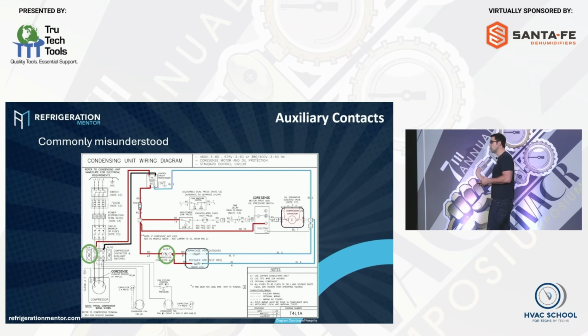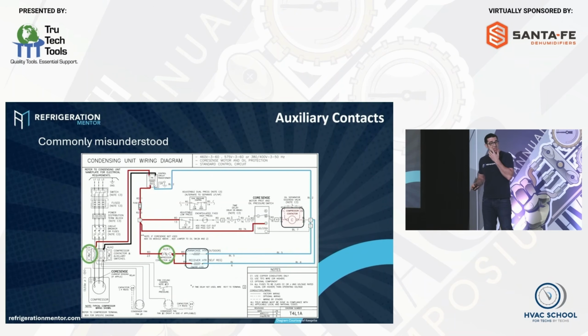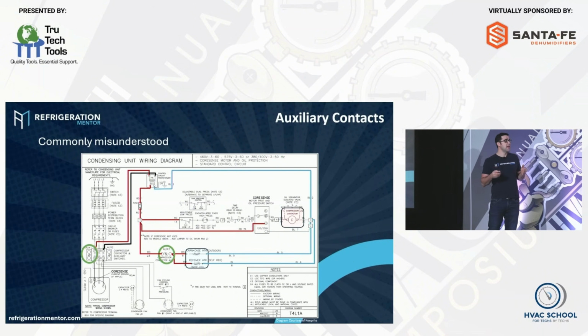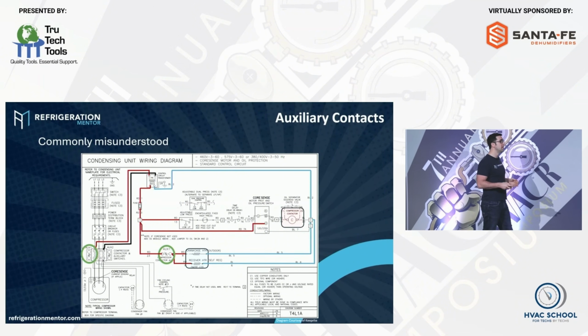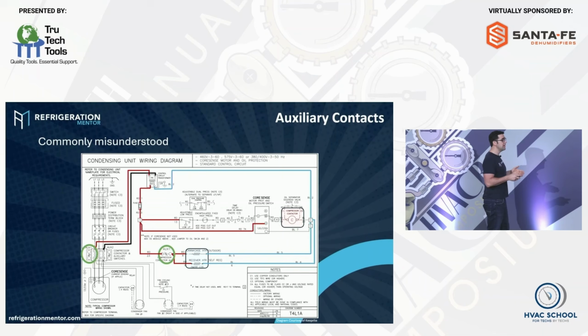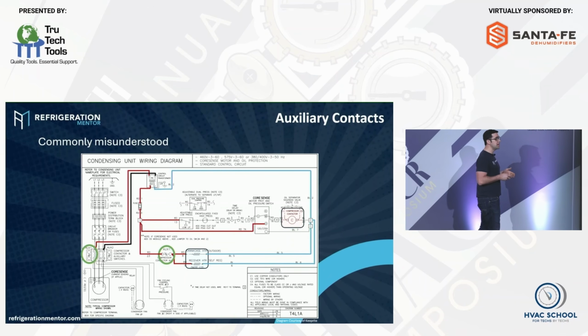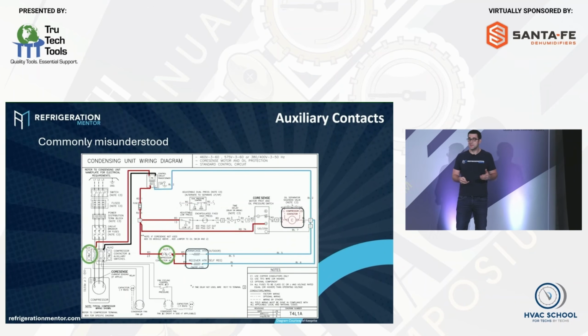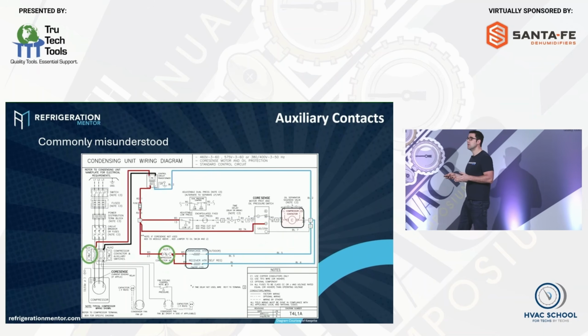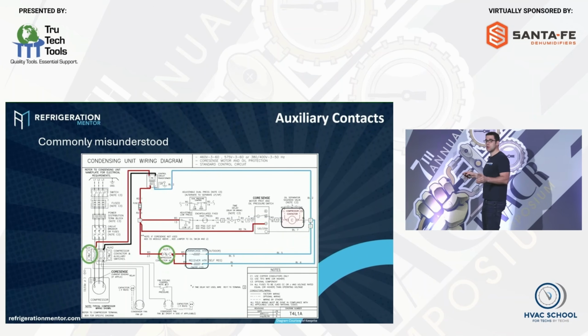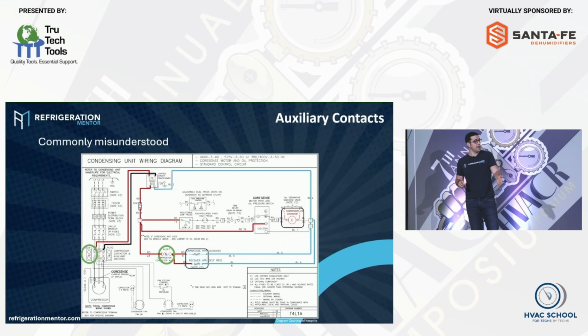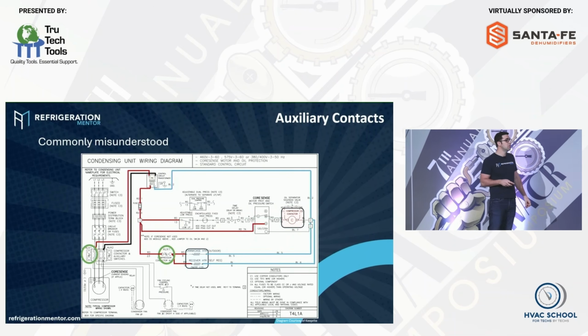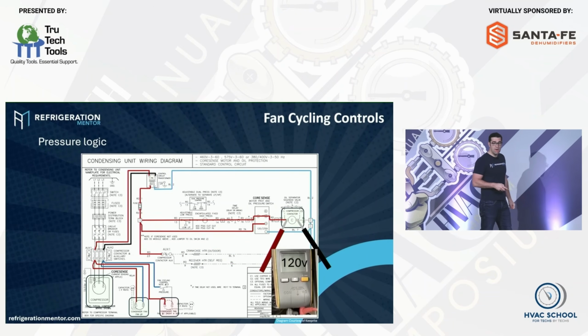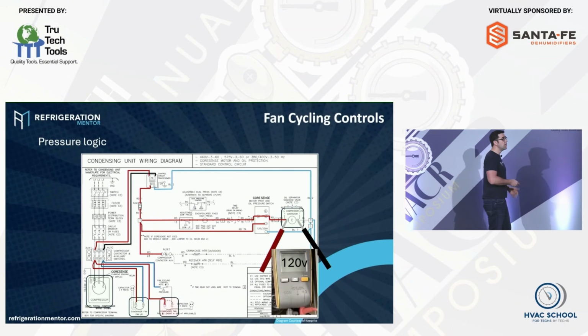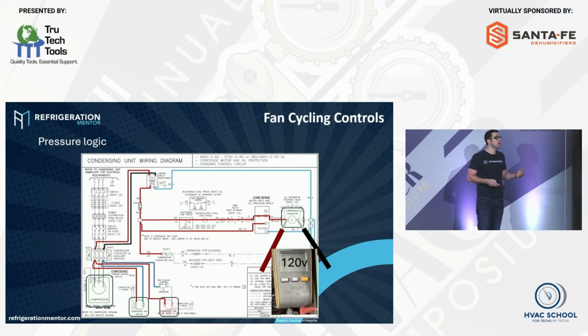One of the things that's really important is to understand how the switches work. Every wiring diagram that you see is in the de-energized position. In the de-energized position, this here is closed. So when nothing is on, those are closed. In this example here, your crankcase heater and your receiver heater would be running. When it's powered up, all of a sudden, those wouldn't be working. They would be opened up.